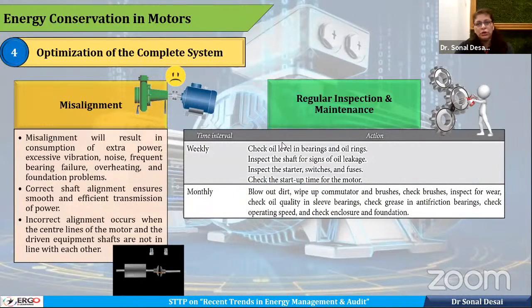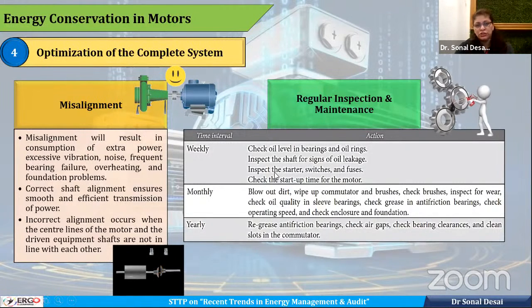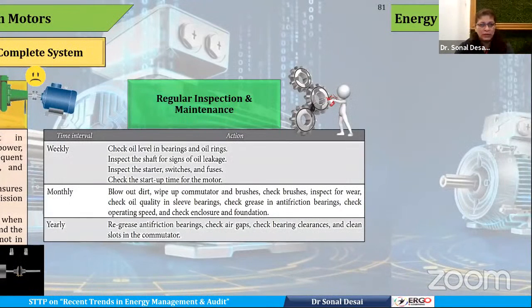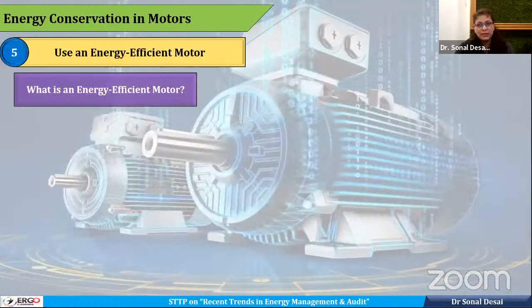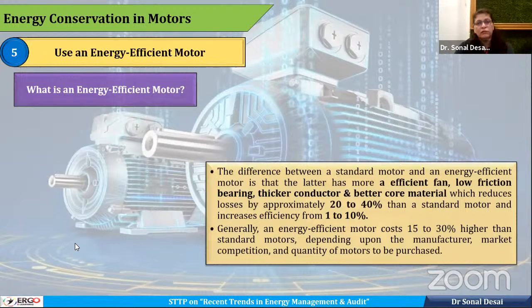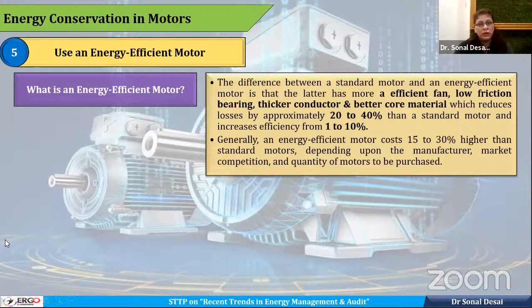The weekly schedule will have basic checks like oil level check, inspection of shaft and starter, etc. Monthly check will be removing dirt and cleaning certain parts, while yearly maintenance will have regreasing or changing the lubricant, etc. So maintenance is always better than unscheduled downtime, and we should take that wisely. And this is the last and most important part of the motor segment, that is use of energy efficient motor. What is an energy efficient motor? Compared to a standard motor, when we have a motor having a better fan, lower friction bearing, thicker conductor and better core material, it will ultimately have losses reduced by 20 to 40%, and it can increase the motor efficiency by 1 to 10%. So it is always good to have an energy efficient motor, and a better working condition is achieved.